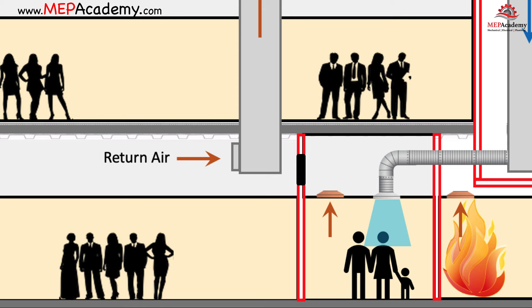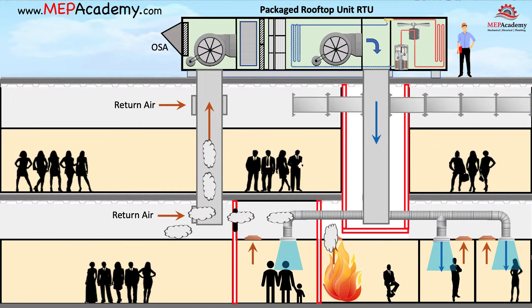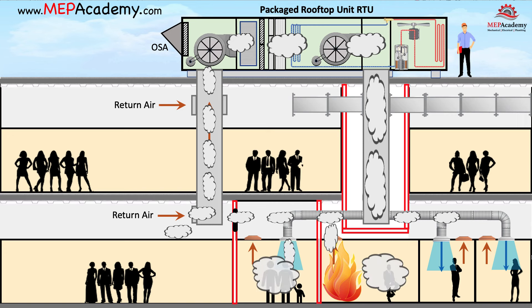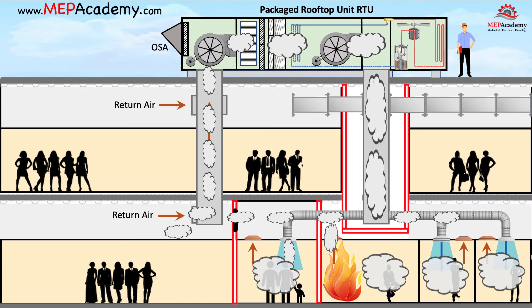If we don't protect the openings we made in the walls for our air conditioning ducts, then smoke and fire could enter the emergency exit corridor, compromising the safe exit of the occupants. Since the return air is under negative pressure, the smoke could be sucked back into the air conditioner and sent back down the supply duct to all the spaces, compromising the safety of all the occupants.